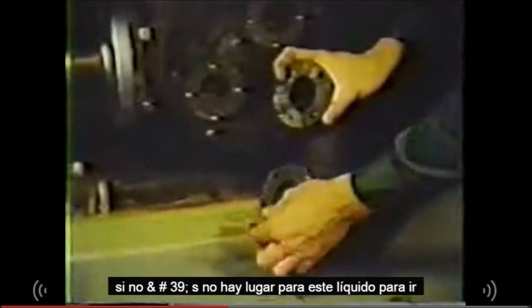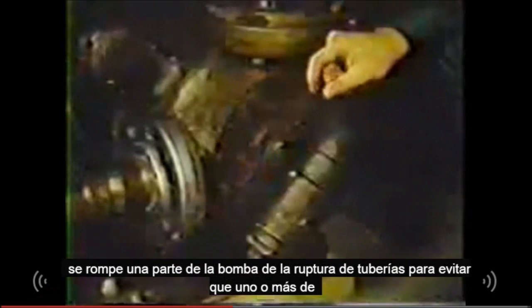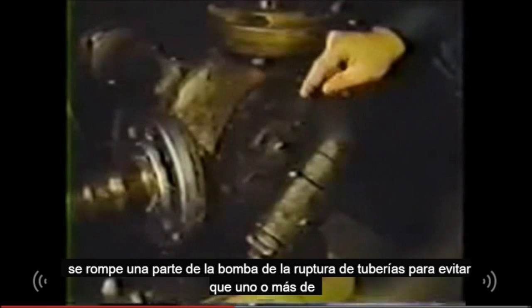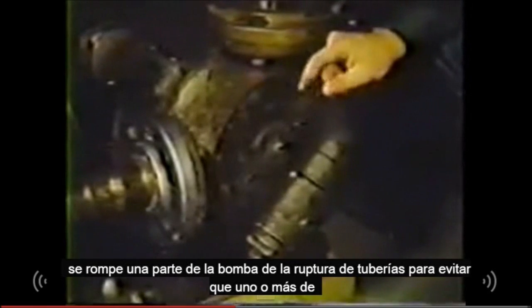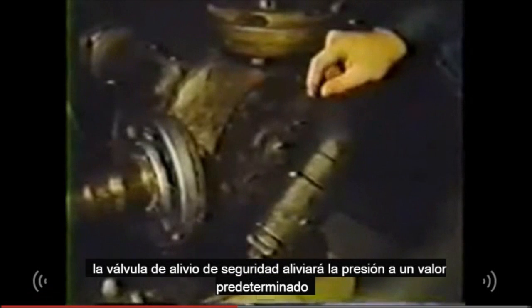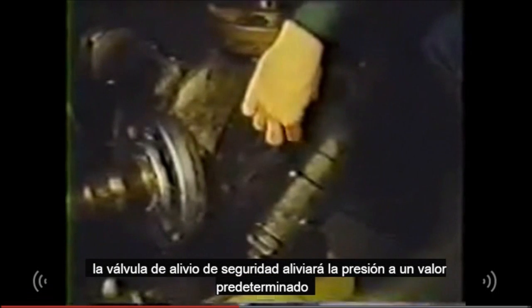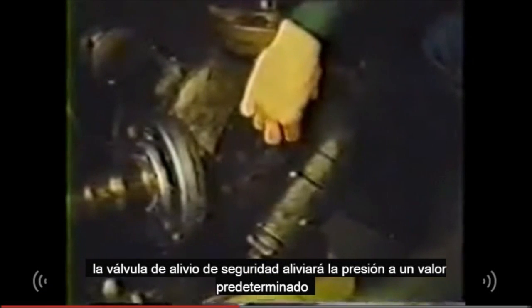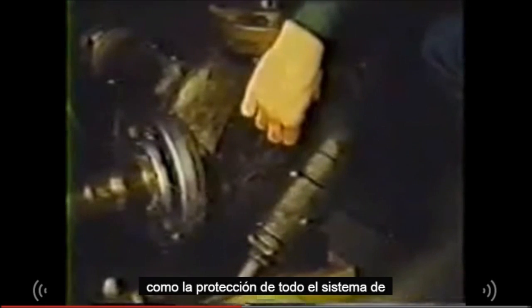A rotary gear pump is a positive displacement pump. This means that when the pump is rotated, liquid will be delivered to the discharge side of the pump. If there's no place for this liquid to go, the pressure will build up until the motor stalls, the drive equipment fails, a pump part breaks, or the piping ruptures. To prevent any one or more of these things from happening, a safety relief valve will relieve the pressure at a predetermined value, thus protecting the entire system.